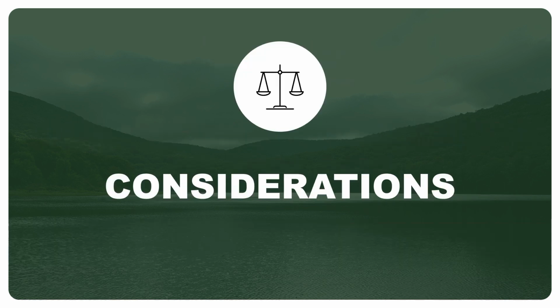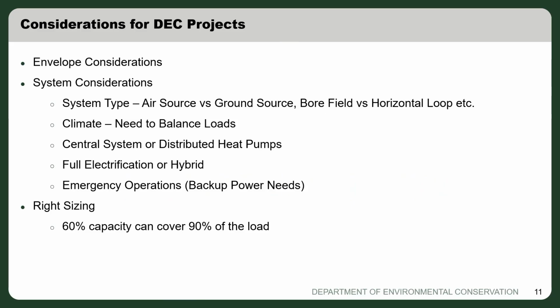Before I get into some specifics on some of our projects, I'll talk a little bit about some of the considerations that we really have to take into account whenever we look at a new project. Big thing is envelope. I heard a great quote yesterday that I like. It's, don't electrify waste. And it's absolutely right. So the first thing we look at is the envelope. What makes the best bang for the buck? Seal your building up, insulate it, replace the windows if they're that bad. Air seal, very important. Spend the time. That's not sexy, but it's important. Reduce your load, because electrifying is not inexpensive. It's very expensive. So if you invest the money in the envelope, you can greatly reduce the load that you need. I was also talking to Indu earlier, in some of our historic buildings that have old radiators, if you insulate the building, you might be able to satisfy the heating needs of that building with 130-degree water instead of 180-degree water. So you can save the historic characteristics of the building.